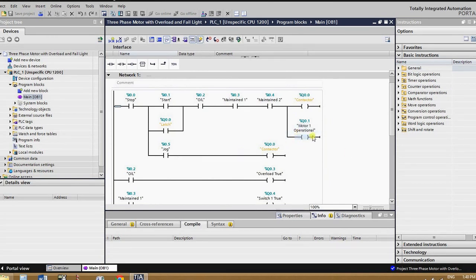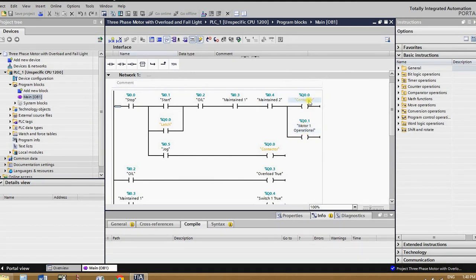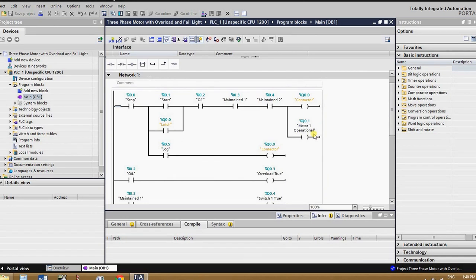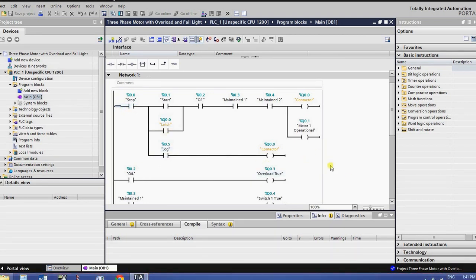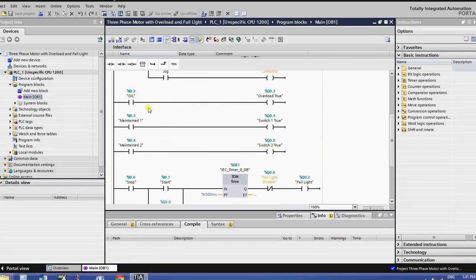I have an output here that goes to a light that tells us that the contactor that latches motor 1 is operational. When that green light comes on it means your first motor is spinning. I also hooked up a jog here in series with our start, and that goes straight to the contactor. So when you push the jog, if the stop is not pushed, it'll just spin the contactor and nothing else. I've also added some inputs here that just basically go to lights.